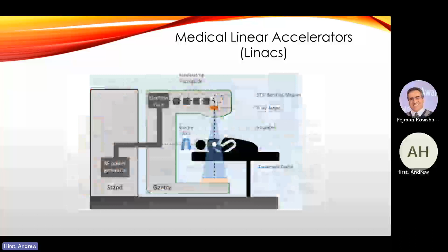Essentially you have a power generator that feeds into an electron gun, as well as the waveguide itself, and sets up resonance of a microwave, which accelerates those electrons. They're then bent downwards to the patient and hit a target to produce the photons. They're also collimated, so you end up getting this conical shaped beam coming out, and then collimated again, so that beam is defined as a square or a rectangle. So when we talk about field size, we're talking about in one plane of that beam, what it would look like as a cross section. So they're rectangular or square size.